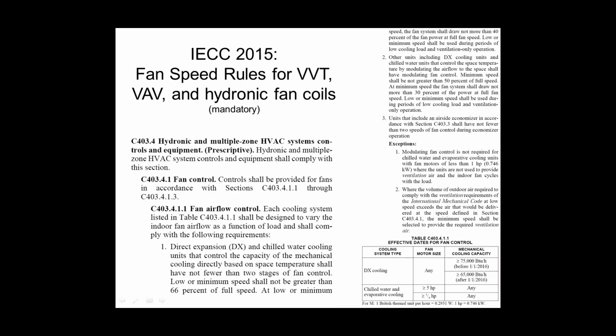Another interesting rule that specifically comes in when we're talking about VAV airflow systems and VVT zoning systems, as well as hydronic fan coils. The way this is worded is so weird. The section itself is labeled hydronic and multiple zone HVAC systems. So anything that's hydronic, meaning it has a chilled water coil or a hot water coil, and anything that's non-hydronic that has multiple zones, so a dampering system. Those two fall into this scenario.